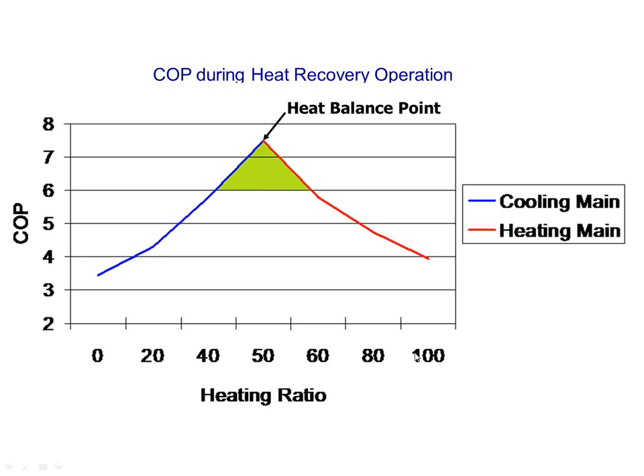Down on the bottom axis is the amount of heating versus cooling, right? So blue is my cooling line, red is my heating line. This is a heat recovery system, so it's a 3-pipe system that does simultaneous heating and cooling. When I'm in the full cooling scenario, which is the 0 column there, it shows my efficiency for my cooling system.